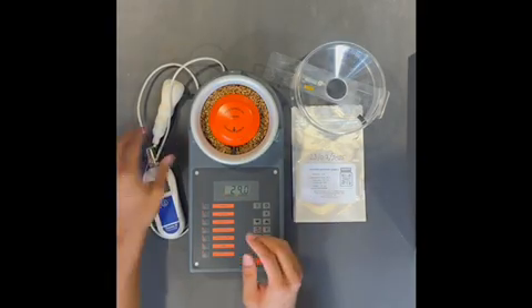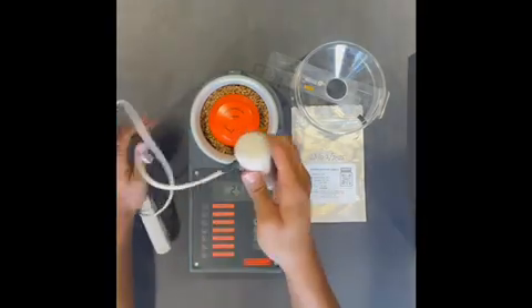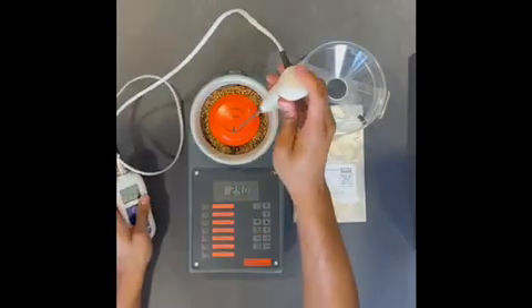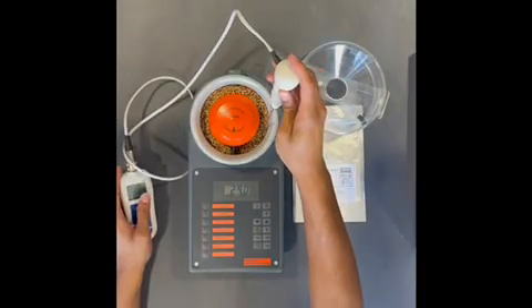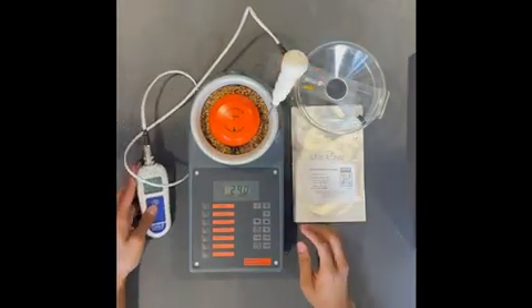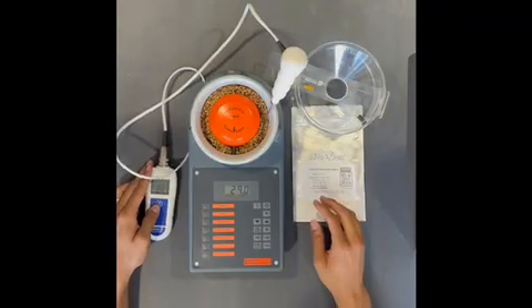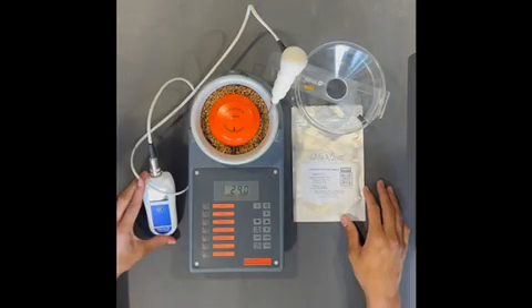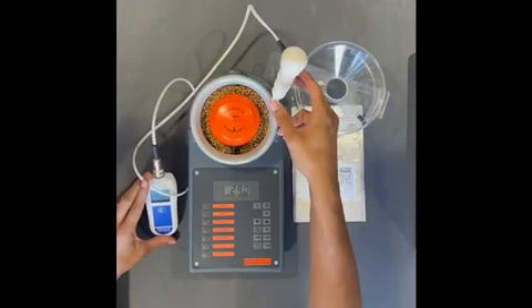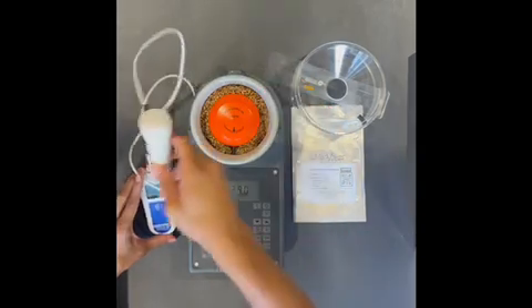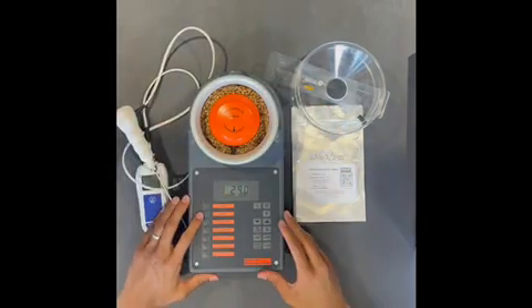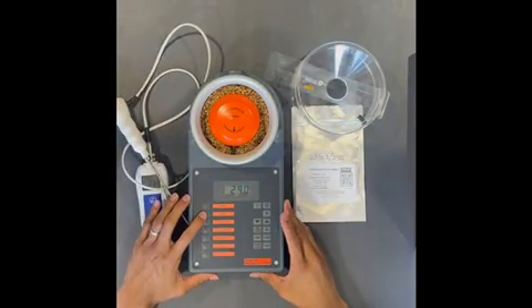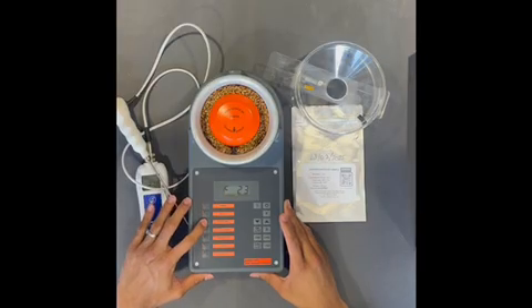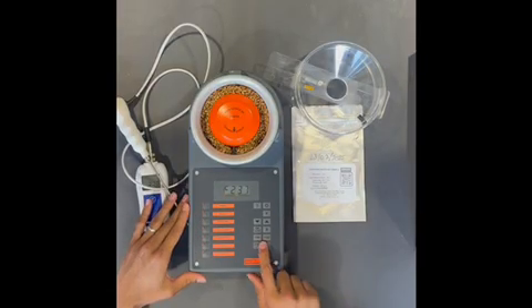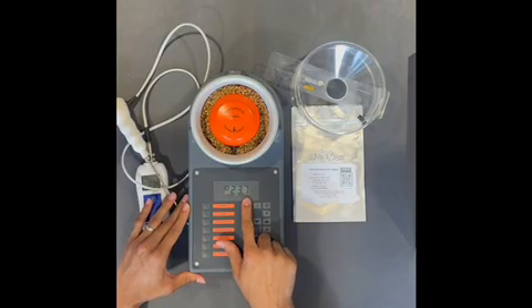At this stage, we want to take our temperature probe, and we want to get an accurate reading of the sample. So we'll leave the temperature probe in there for about 30 seconds. Perfect, so the temperature is settled at around 23.7. So we'll go ahead and input those values into the machine by pressing 237 and pressing temperature, and that will turn to 23.7.